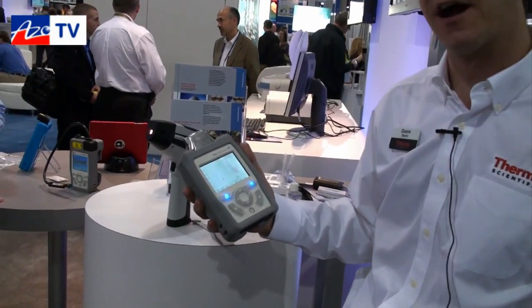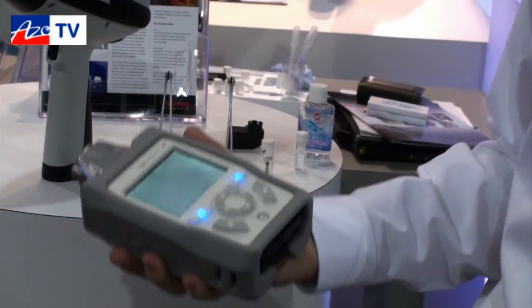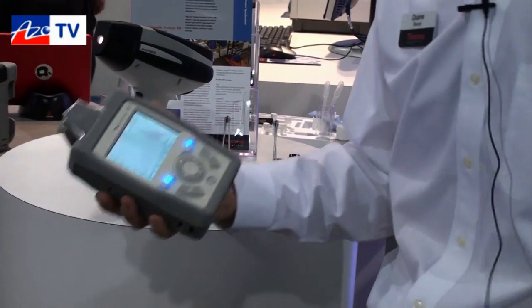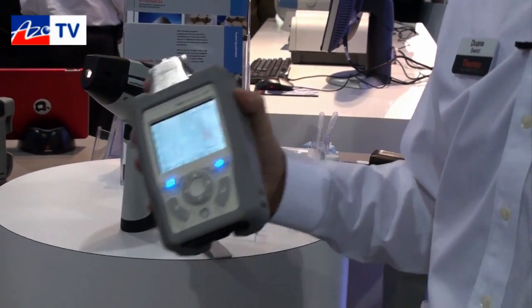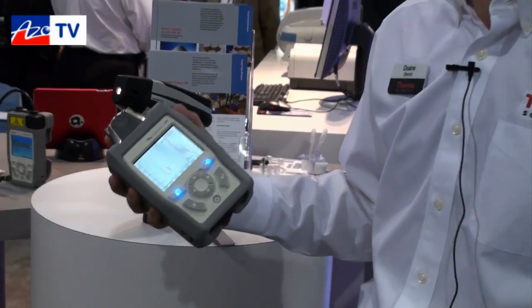This is the world's smallest FTIR, but just because we made it small, we did not want to compromise the analytical attributes of the instrument. For those that understand spectroscopy, this is a 650 to 4,000 wavenumber instrument with 4 wavenumber resolution — equivalent to a very good benchtop instrument.